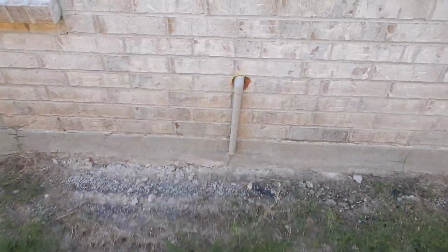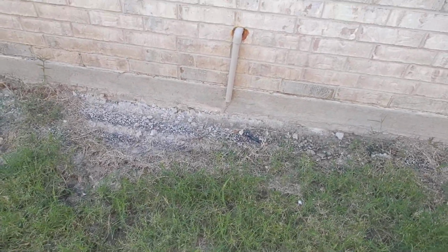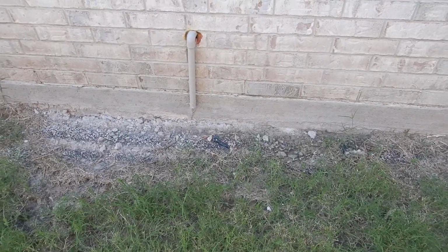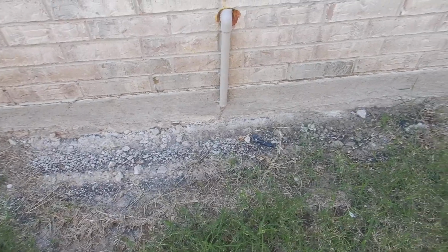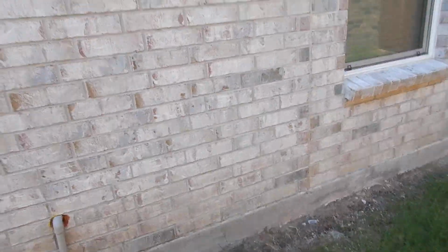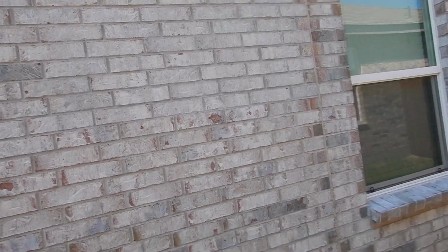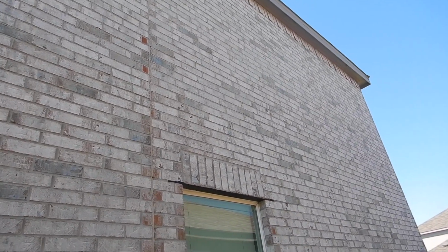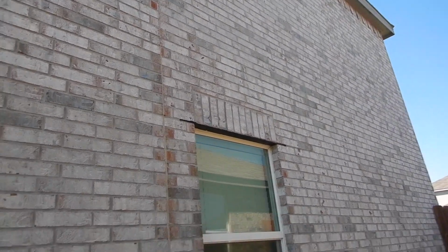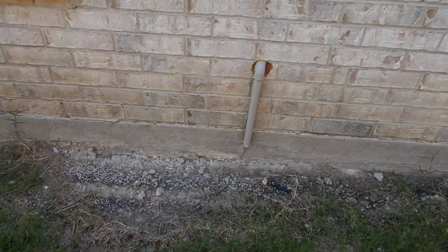You see, initially I would think, and I reserve the right to change my mind, that this pipe was part of the water heater. The reason I think it's part of the water heater is because it's so close to the ground. But I'm over here, and the HVAC indoor air handlers are on this side of the structure. This is the east side of the structure, and I'm not seeing a secondary drain for the water heater.